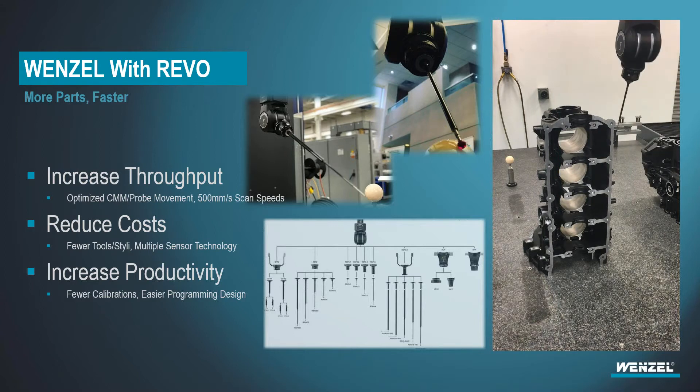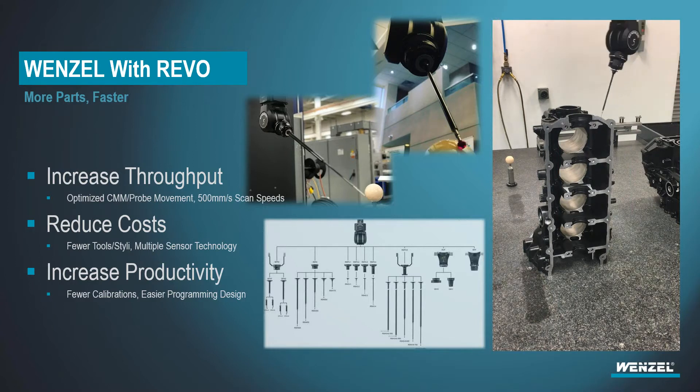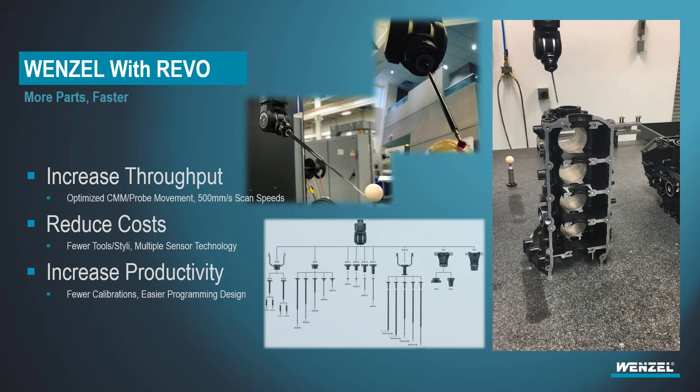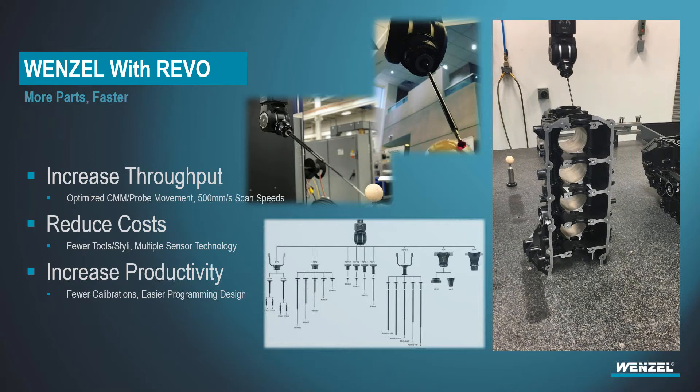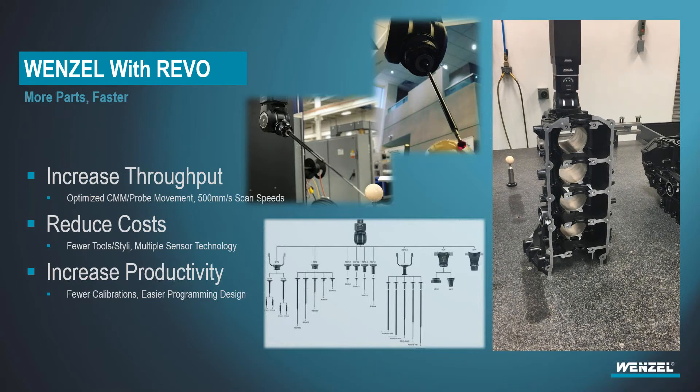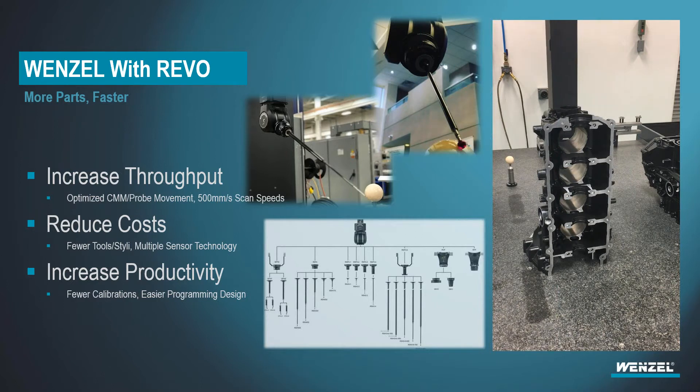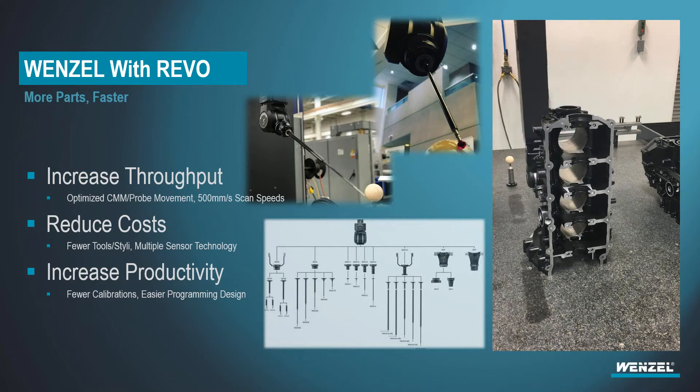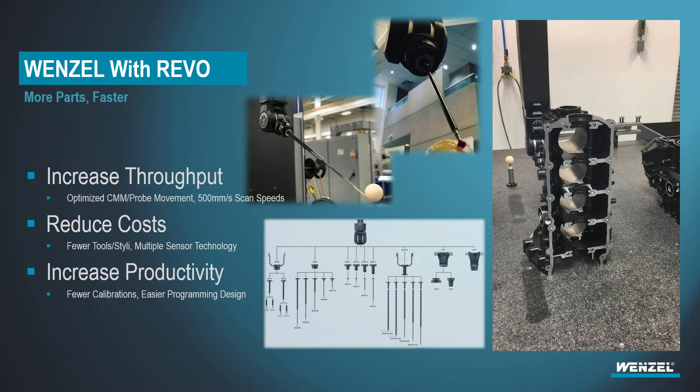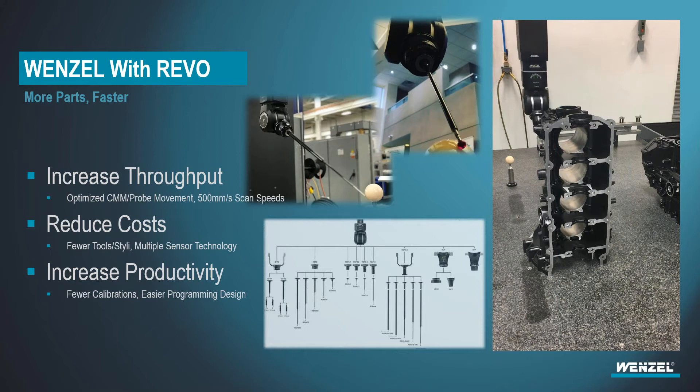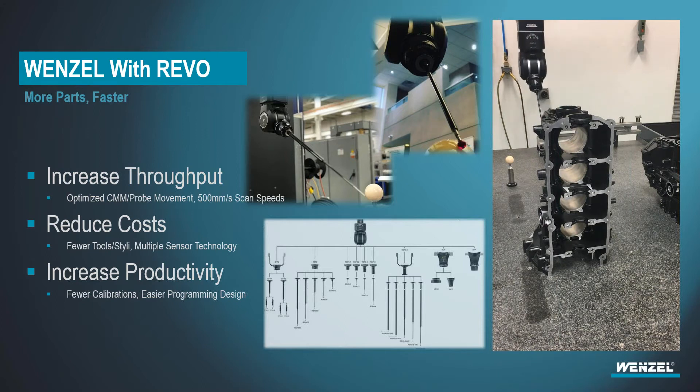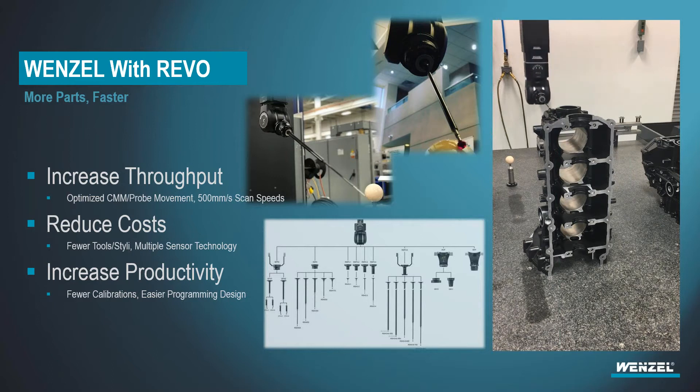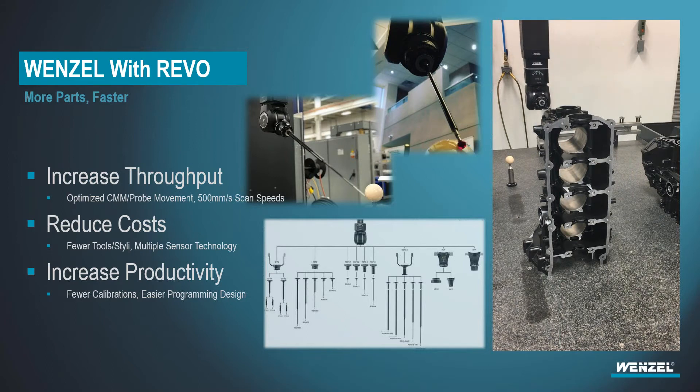One of the benefits of the REVO and the five-axis systems, as you can see the probing dance around here, is most CMMs are equipped with a three-plus-two axis system. That basically means that the CMM itself is going to move in three axes, X, Y, Z, and then your PH-10 or your fixed head probing moves in two of its own angles. The REVO and five-axis system is really kind of a true five-axis probing system. And as you can see a little bit in this video, the CMM is able to maintain movement while the probe head itself is moving to its new location.